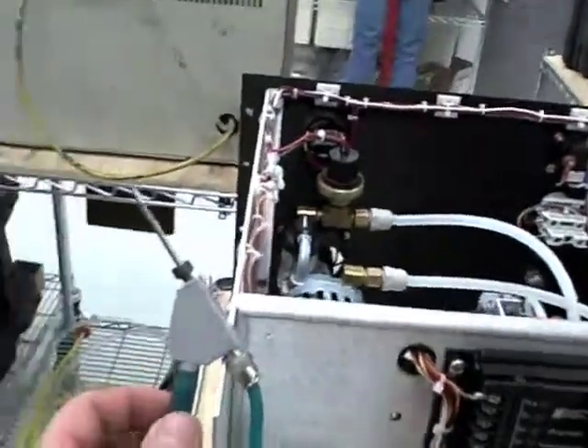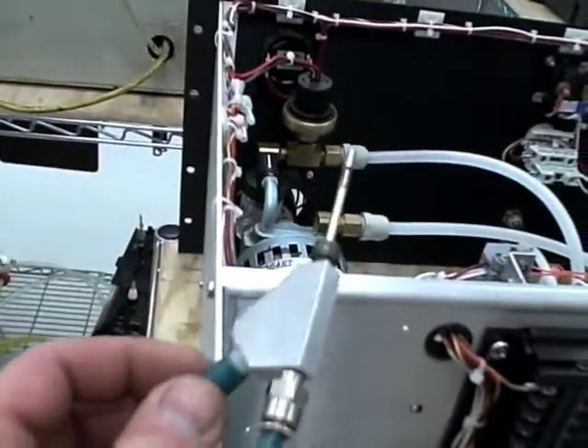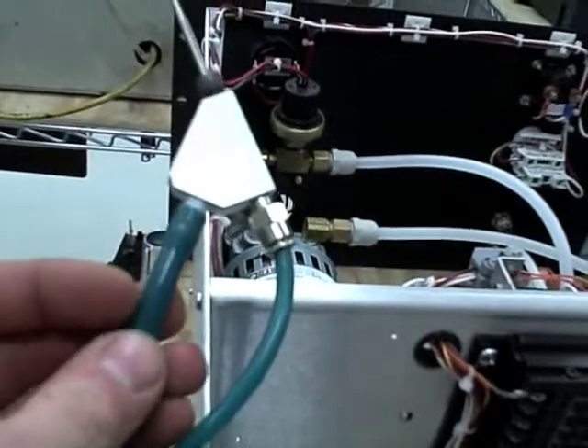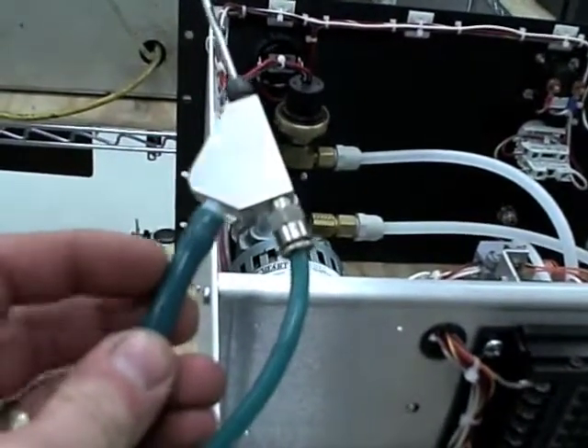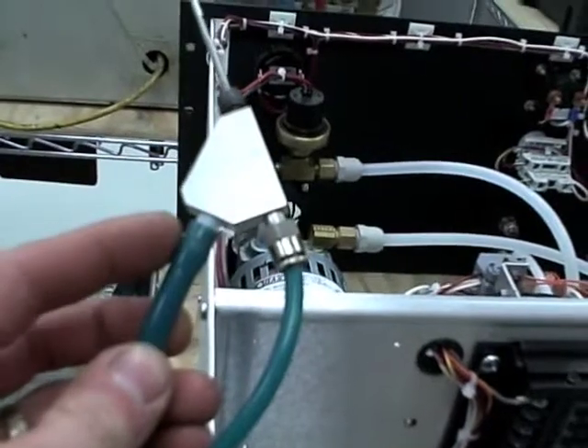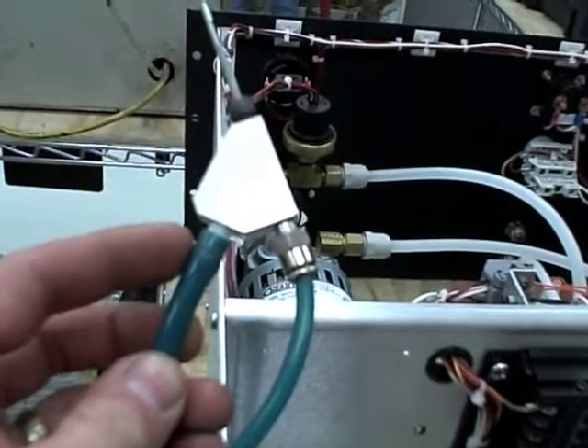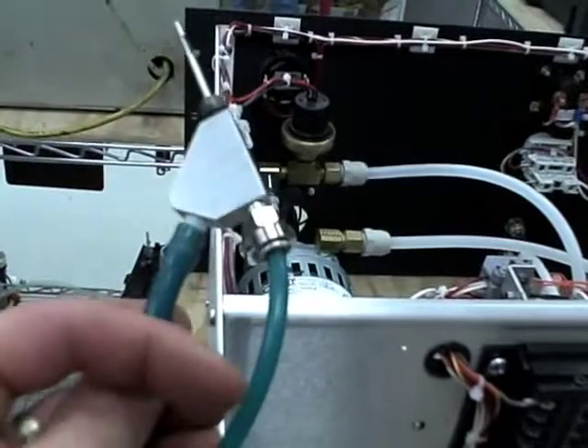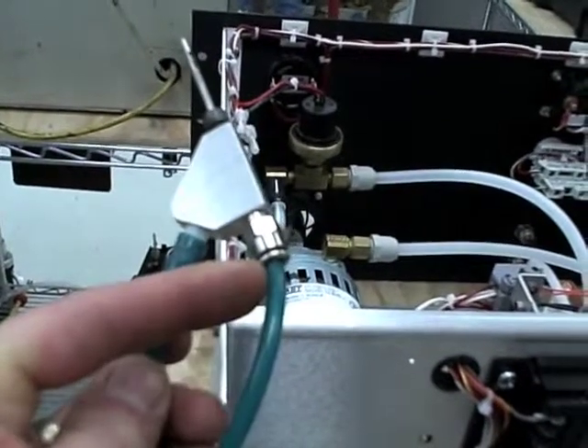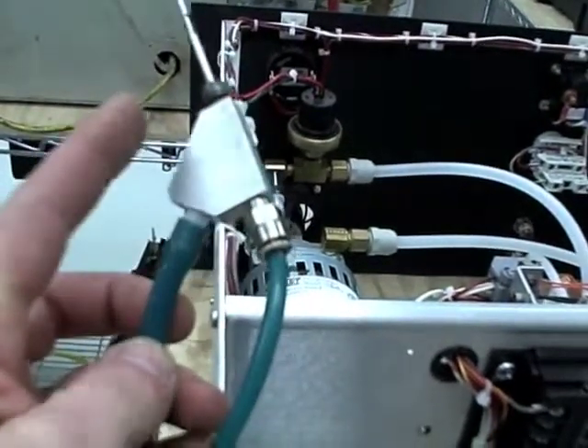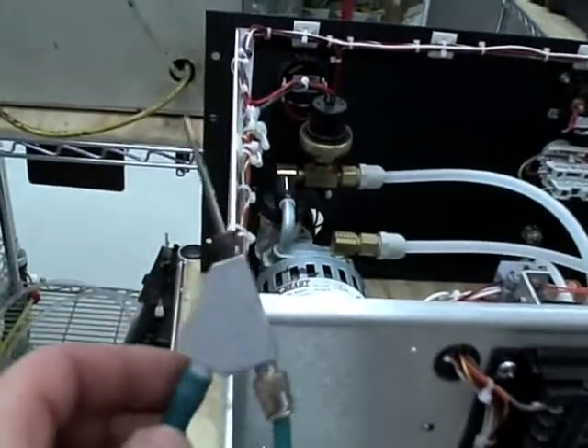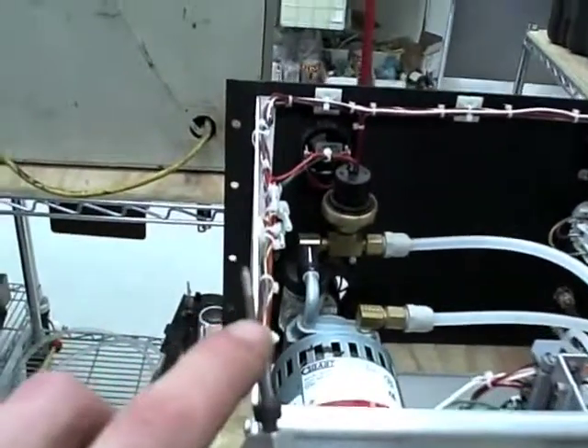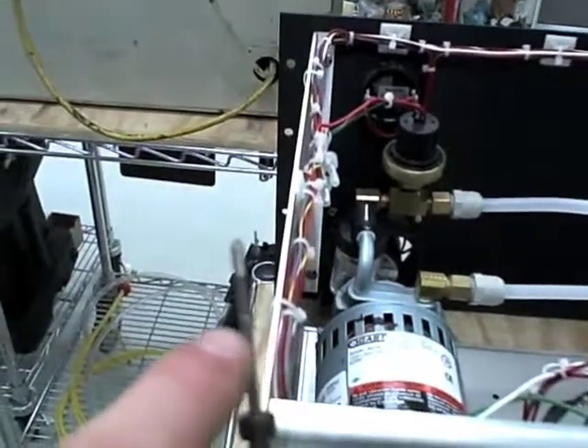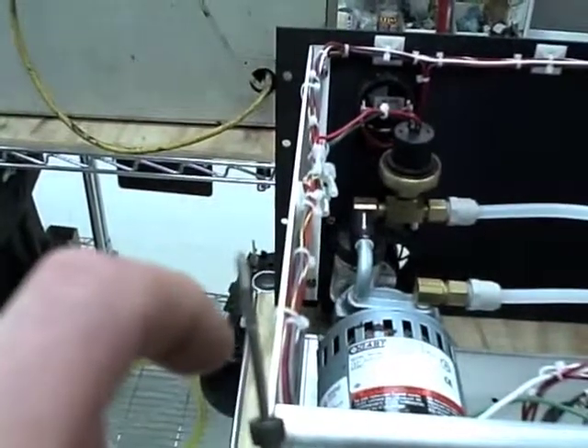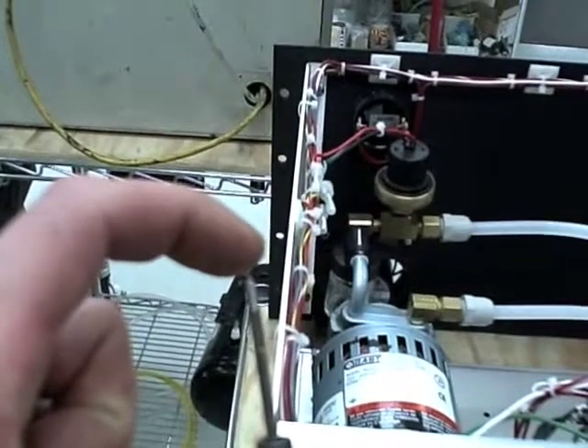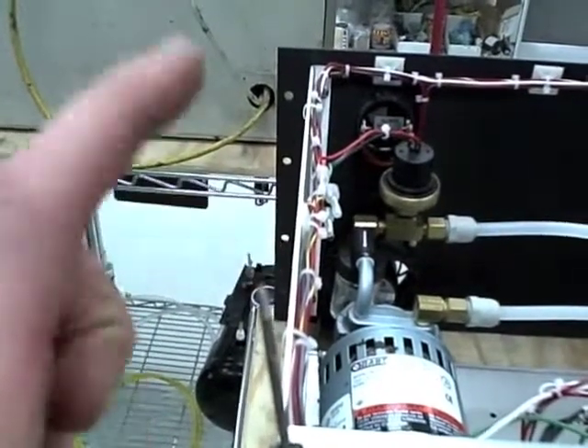If we were to look up close at this one hole filling lance first before we start the calibration, you'll notice two hoses. The bigger hose is a 3/8 inch outside diameter hose, and that's where the vacuum is going to be sucked back into the machine. And the smaller hose is where the argon comes out of the machine. And if you look at the tip of this lance, you can see a little slot burned in, and that's where the vacuum gets sucked in. And then out of the center of the end, there's a small hypo needle, and that's where the argon blows out.